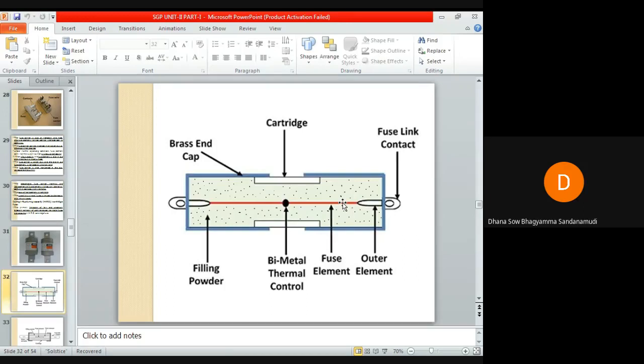So whenever a fault occurs, the excessive current will increase the temperature of this fusing element. It gets overheated and hence it melts. In order to break this fusing element, a bimetal thermal control is placed at the center of this fuse element so that it will help the fuse to immediately break the circuit, because as soon as the fuse is melted, an arc is struck between these two terminals.